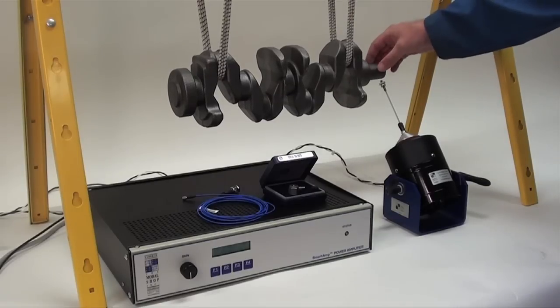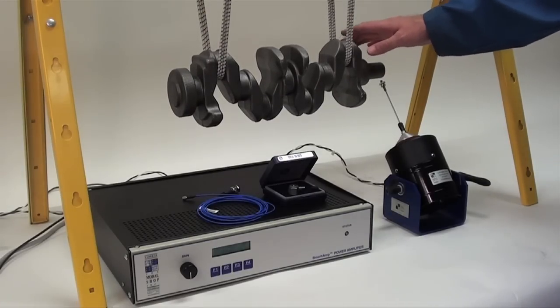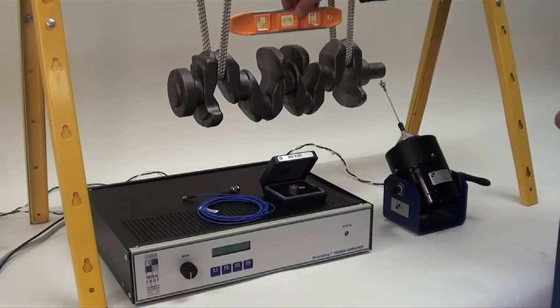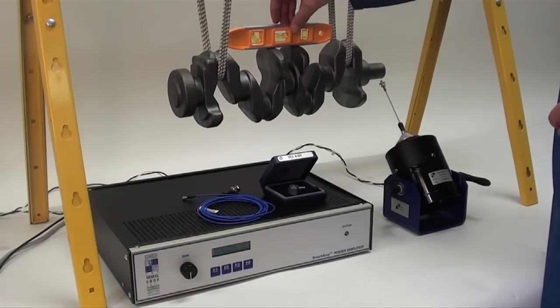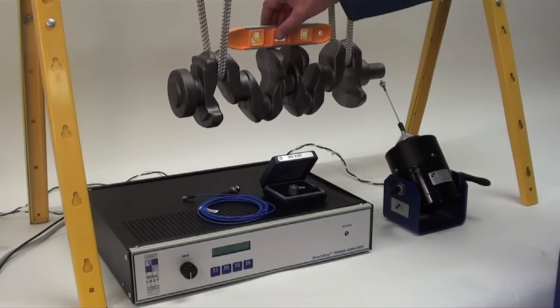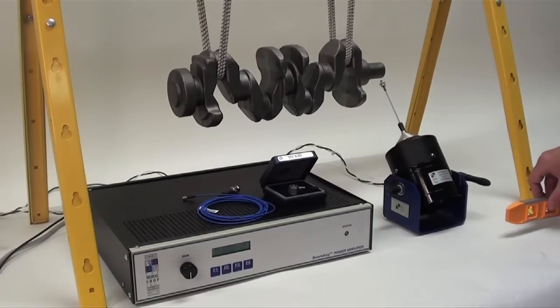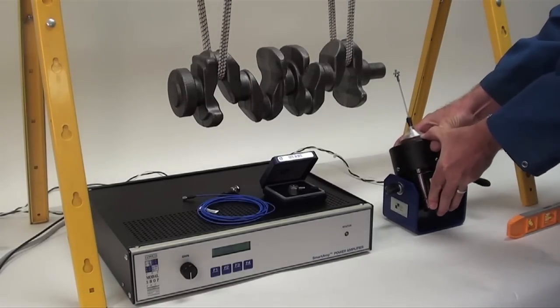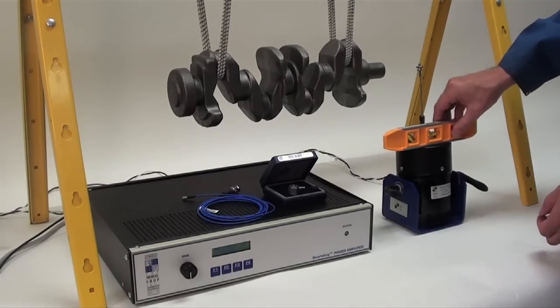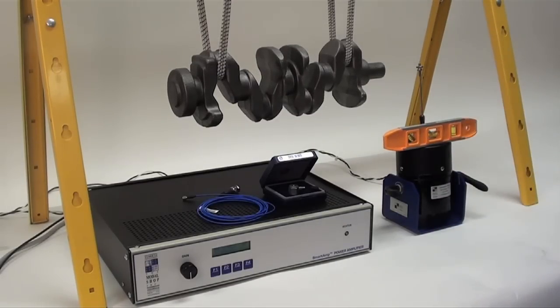In order to facilitate alignment between the test article and the shaker, it's a good idea to use a bubble level. It looks like our crankshaft is hanging level, and we want to be sure that the shaker body is also level with the test article, and it looks like we have a pretty good level.